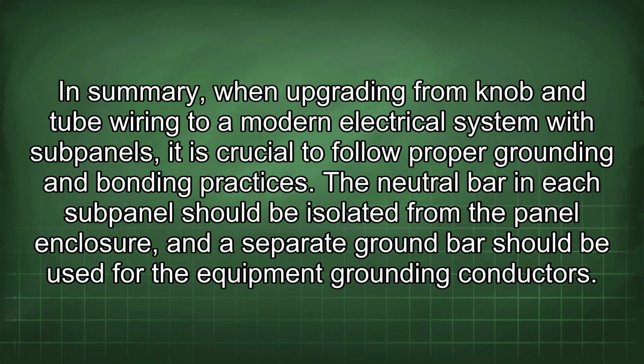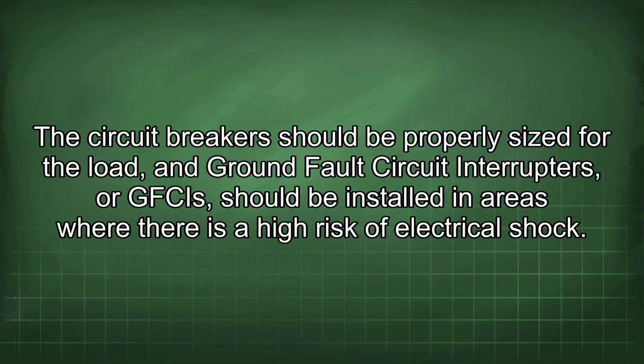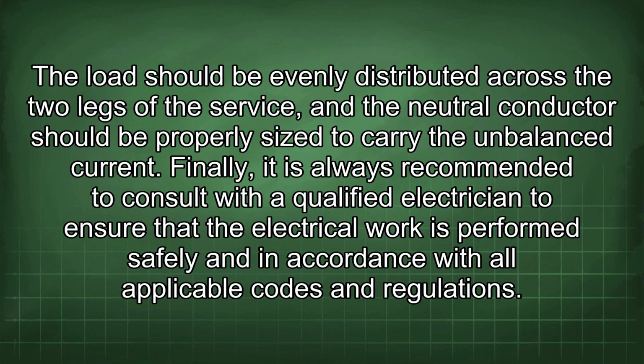In summary, when upgrading from knob and tube wiring to a modern electrical system with subpanels, it is crucial to follow proper grounding and bonding practices. The neutral bar in each subpanel should be isolated from the panel enclosure, and a separate ground bar should be used for the equipment grounding conductors. The circuit breaker should be properly sized for the load, and GFCIs should be installed in areas where there is a high risk of electrical shock. The load should be evenly distributed across the two legs of the service, and the neutral conductor should be properly sized to carry the unbalanced current.